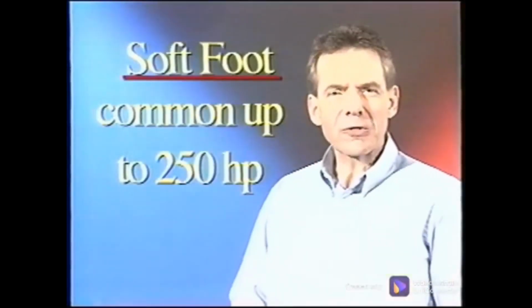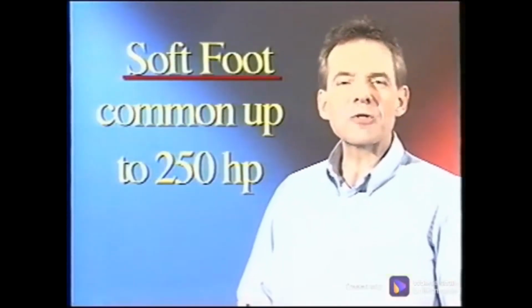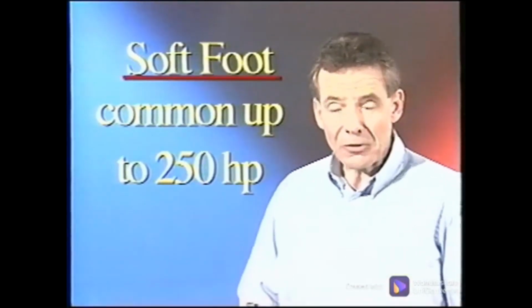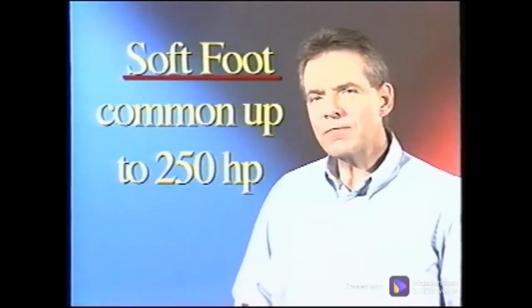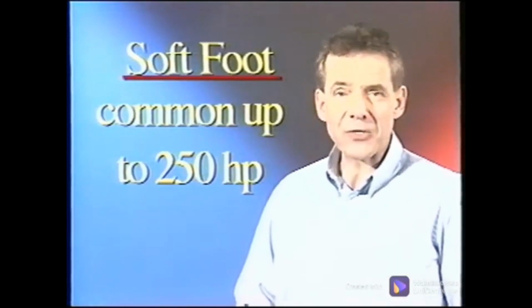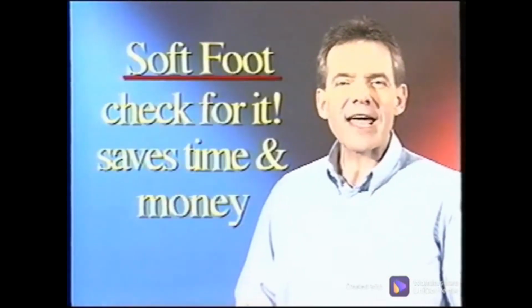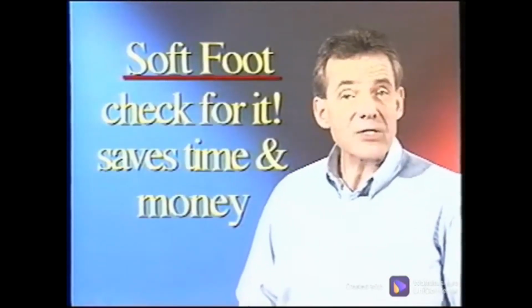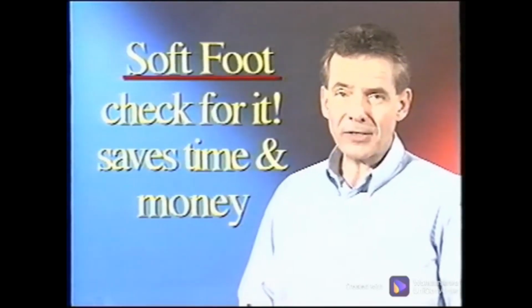peak. A soft foot problem is very common in motors up to 250 horsepower. It occurs in larger motors, but the stiffness of larger motors minimizes this occurrence. Because the analyst knew how to check for this, he saved the company the cost of a motor rebuild.